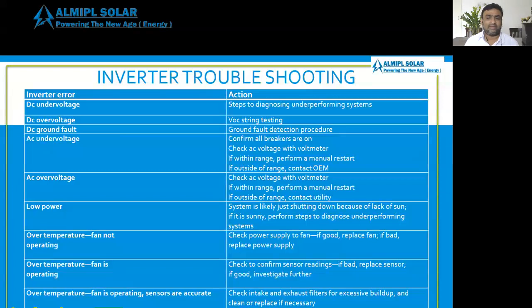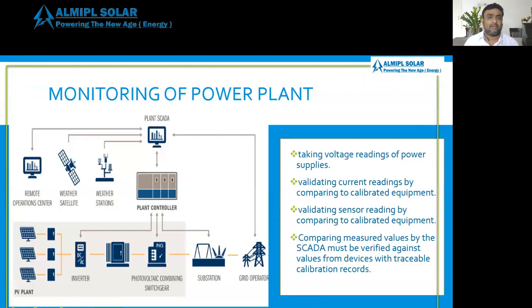Low power: the system is likely just shutting down because of lack of sun. If it is sunny, perform the steps to diagnose an underperforming system. Over temperature, fan not operating: check power supply to the fan. If good, replace the fan. If bad, replace the power supply. Over temperature, fan is operating: confirm the sensor reading. If bad, replace the sensor. If good, investigate further. Over temperature, fan operating, sensor accurate: check the intake and exhaust filters for dust buildup, and clean or replace as necessary.